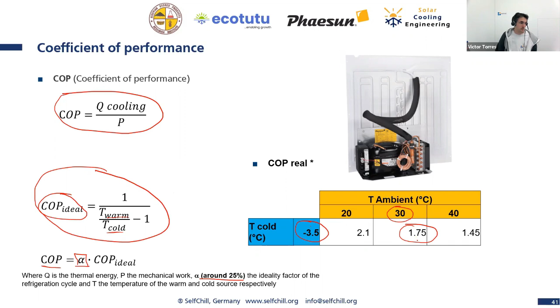This means if we consume 1 watt of electricity, the cooling unit delivers 1.75 watts of thermal energy, cold energy in this case. This means if our cold room has a thermal energy consumption of 13.5 kilowatt hour per day, and we consider an average COP of 1.75, which is a worst case, then we'll have a maximum electricity consumption of 7.7 kilowatt hour per day, 7.68 kilowatt hour per day electrical energy.